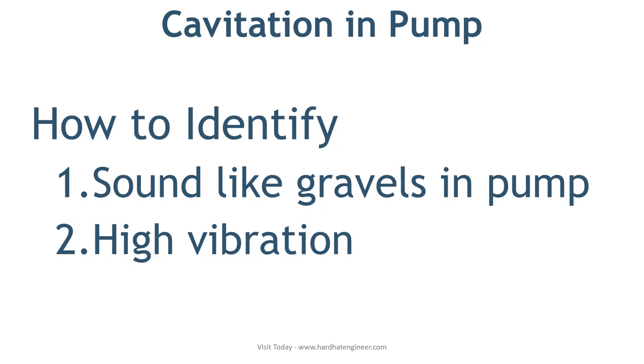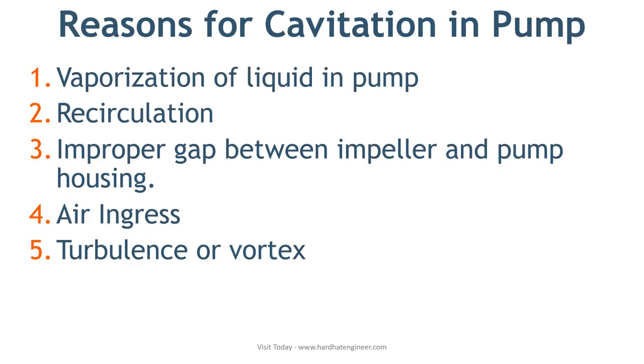Now you know what cavitation is. You should also know why it happens in a pump. There are five main reasons that lead to cavitation. The first is vaporization of liquid in the pump — this is the biggest reason. As explained, if the pressure inside the pump falls below the vapor pressure, the liquid starts boiling and creates vapors. To eliminate this, you have to keep enough head at the pump suction.